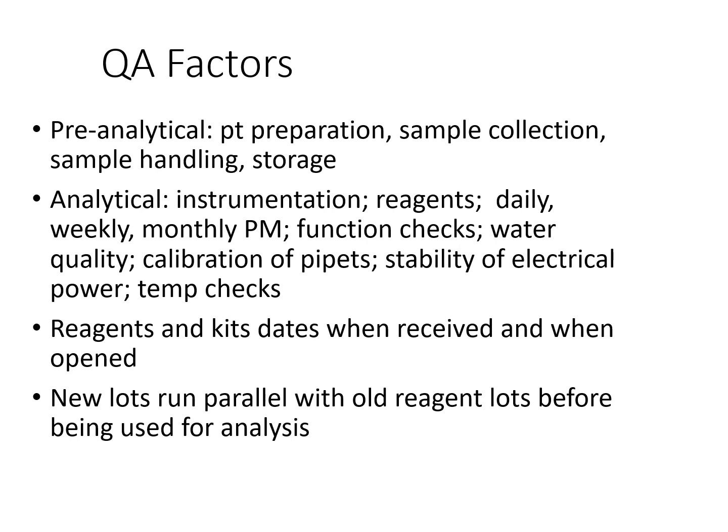The analytical phase involves your instrumentation, your reagents, your daily, weekly, and monthly preventative maintenance on your analyzers, your function checks, your water quality, your calibrations of your pipettes, stability of your electrical power, and temperature checks. Reagents and kits, and everything in the lab, is dated when it's received, and it's also dated when it's opened.